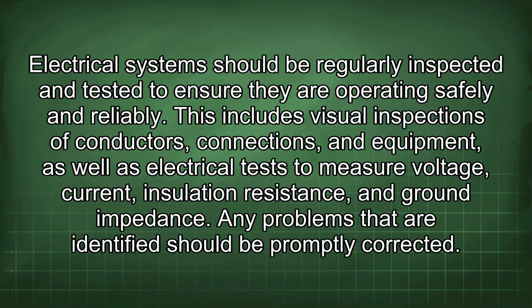Electrical systems should be regularly inspected and tested to ensure they are operating safely and reliably. This includes visual inspections of conductors, connections, and equipment, as well as electrical tests to measure voltage, current, insulation resistance, and ground impedance. Any problems that are identified should be promptly corrected.